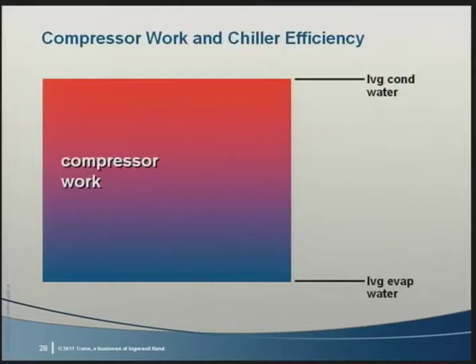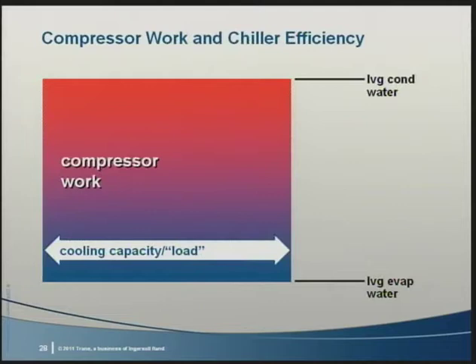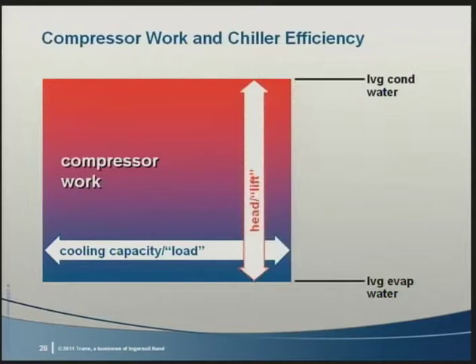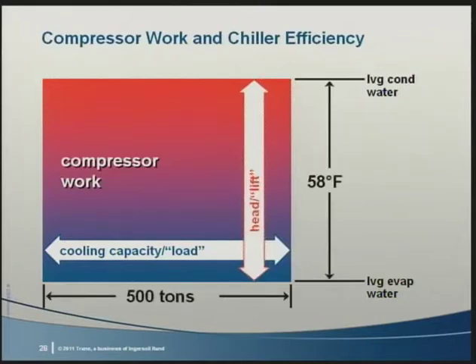Here's a graphic showing the compressor work rectangle to illustrate the relationship. The width of the rectangle represents the mass flow of the refrigerant through the compressor and chiller cooling capacity. The height of the rectangle represents compressor head, or the lift required of the compressor. So referring to the previous example, the load is 500 tons and the lift is 58 degrees.